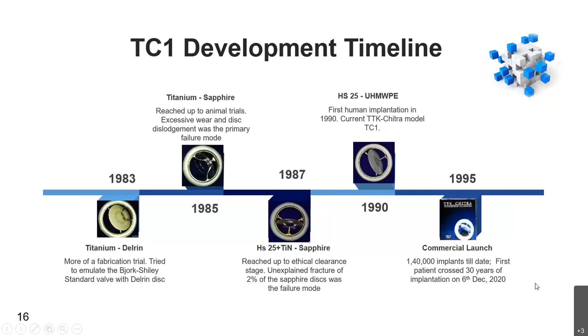When the sapphire disc failed in the titanium nitride sapphire combination, we had to look for a material which is soft, which has good toughness, and will last for 50 or 60 years without any corrosion, degradation, etc. So we chose many materials like Delrin ST, Fluon PTFE, then Delrin AF, and ultra-high molecular weight polyethylene, and did a series of studies to find out the durability of these materials. Finally, this particular ultra-high molecular weight polyethylene came out as the best candidate.